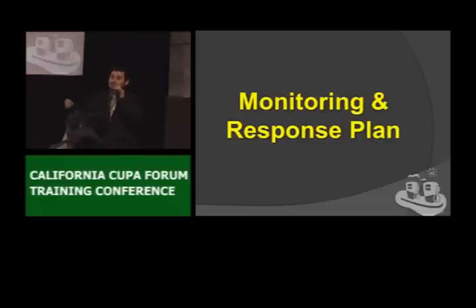So if my signature's on there, I have to make sure that my sites are good and in compliance. So what I'll do is keep it with me or approve it with conditions that it has to be verified upon field verification. Once I go out there and do my inspection, I verify whatever they listed on the monitoring plan and response plan and ensure that that's what is actually on site. We'll go through the entire process of what that looks like.